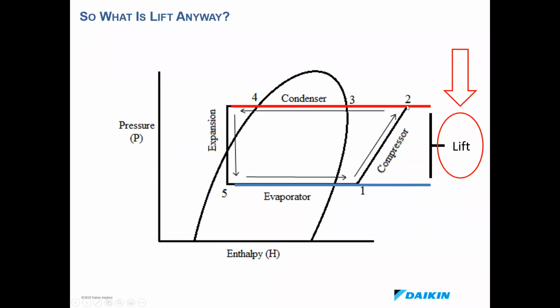So what happens if your ambient temperature drops or your leaving evaporator water temperature rises and your compressor wouldn't need to work as hard? That's what the VVR is doing for you. It's going to help you out in those scenarios. So essentially the compressor is going to have to make up all this work to satisfy this lift condition. So the compressor does work, the change in enthalpy from state 1 to state 2. That's going to be your compressor work.